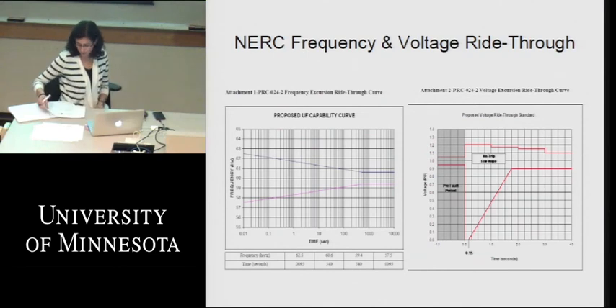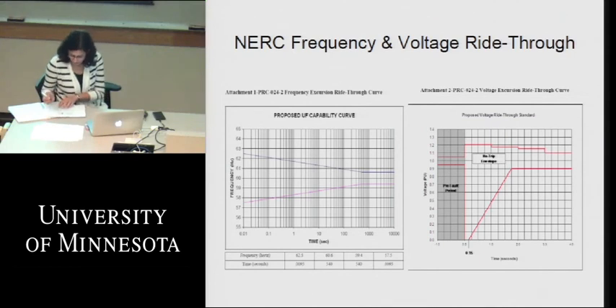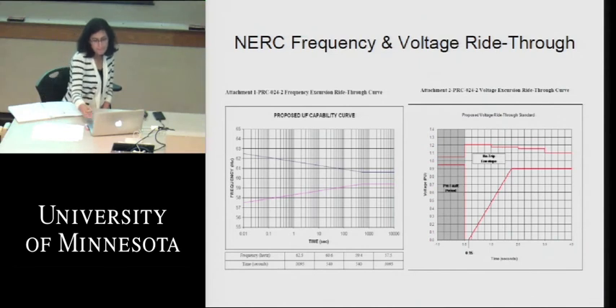And you'll see we've got to operate what we call low voltage ride through all the way. If a fault gives us zero voltage on the system, until the fault clears and the system restores and brings voltage back to our project, we have to be able to not disconnect the turbines and keep them running, so when voltage does recover in a few seconds, we can actually kick off and aid the system in recovery. There's a new concept since 2005. Before that, we just got offline and waited for 10 minutes.